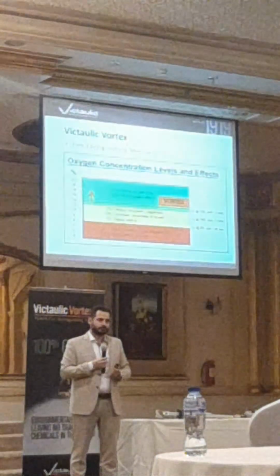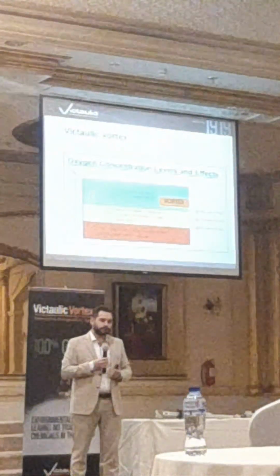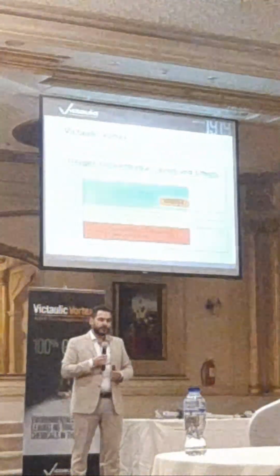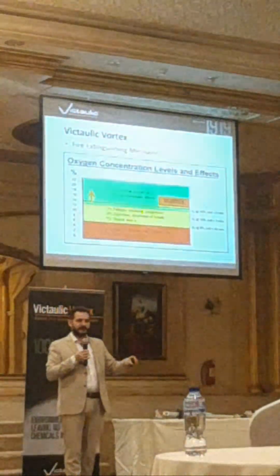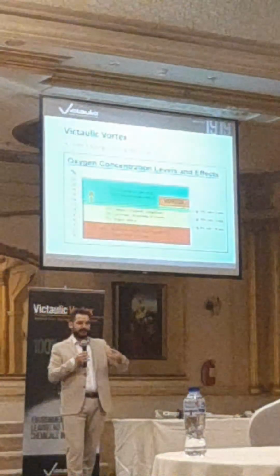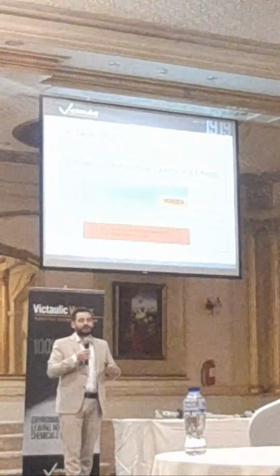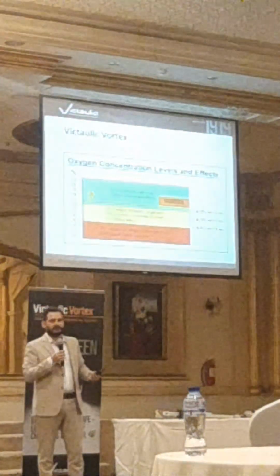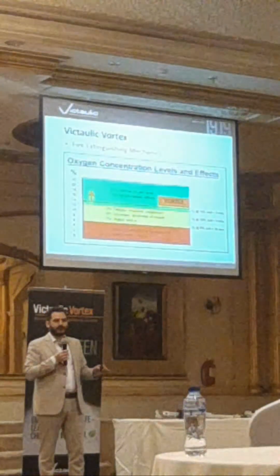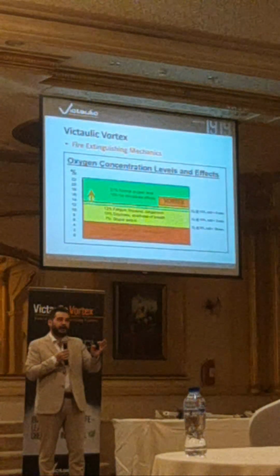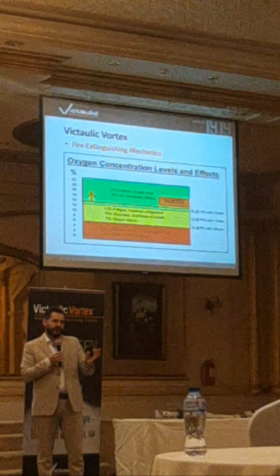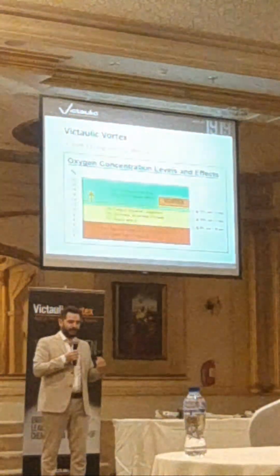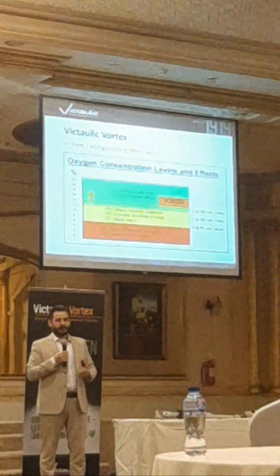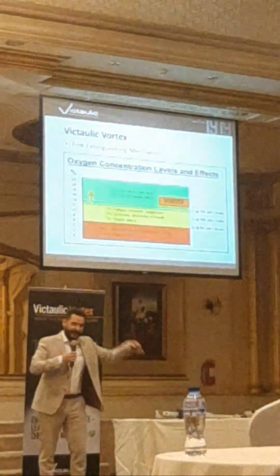How can you make sure you get 100% coverage of the whole room during a fire? So we would calculate how many nozzles you would need to fill that volume within 3 minutes. The most important thing is going to be the amount of nitrogen. The amount of nitrogen is going to decide the oxygen level at the end of the discharge. And then the additional thing will be where we place our nozzles, and the nozzles are going to have that effect.